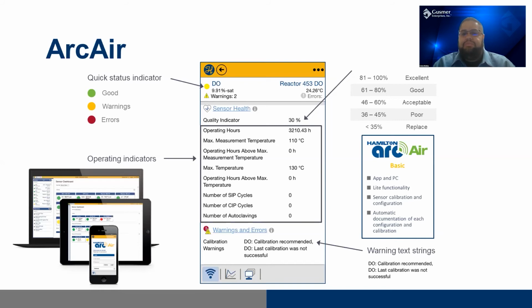Your quality indicator, that's really important. So that tells you when to change your sensor cap. Below 50% is about when you should consider changing that cap. You can get a little bit more life out of it. As you can see on the right, there's a table there where under 35, you really need to replace it. But we typically recommend under 50 because that's where you can see a little bit of performance shift. You can see your maximum temperature. You can see operating hours, CIP cycles, and all that kind of good stuff for each sensor too. And then at the bottom, you can look at your current warning messages and when you should calibrate.